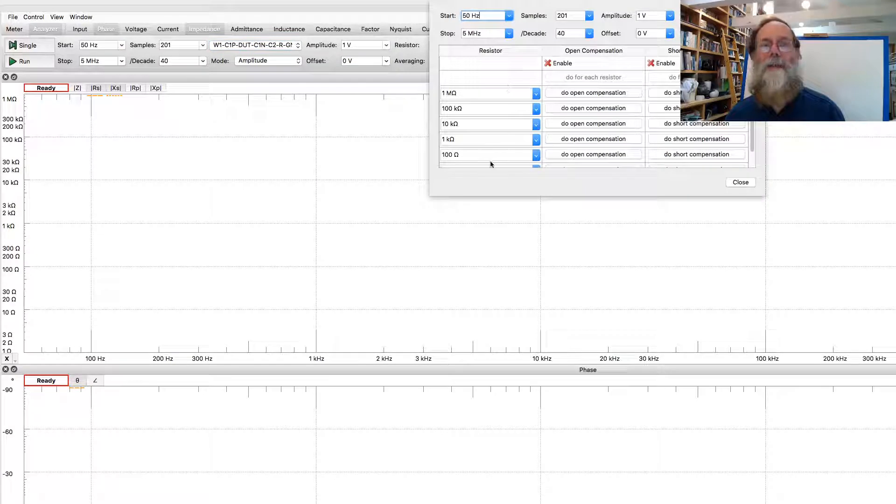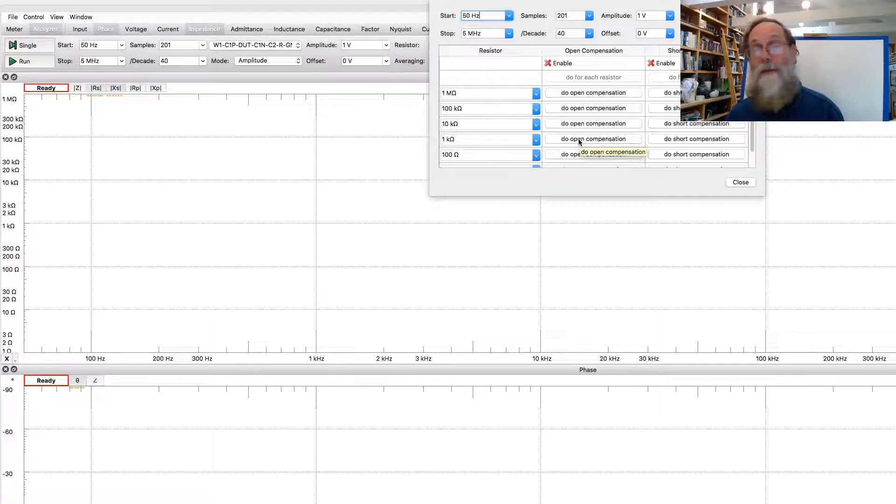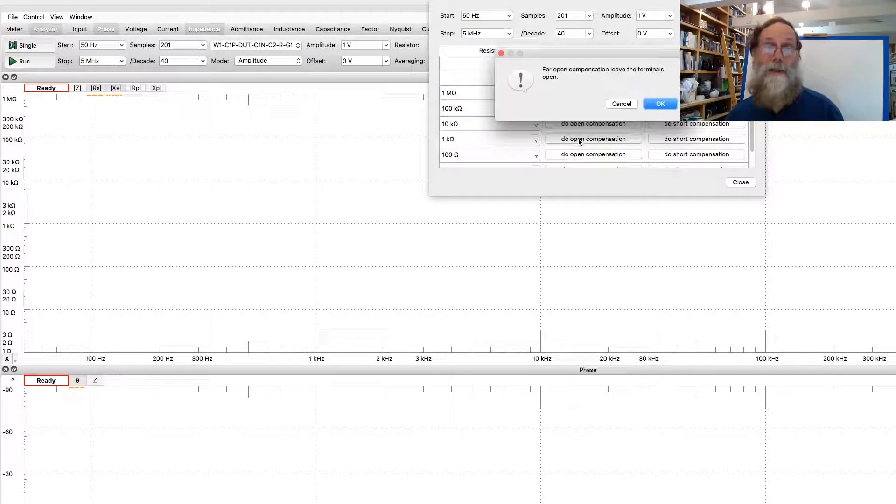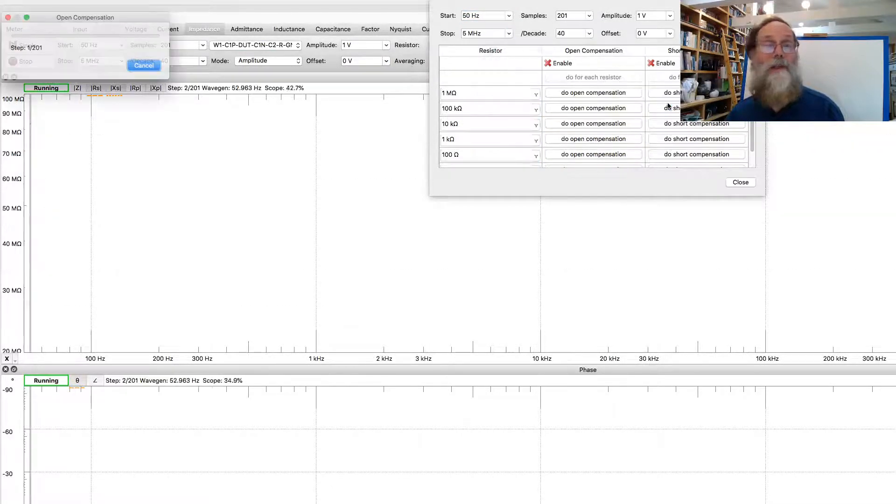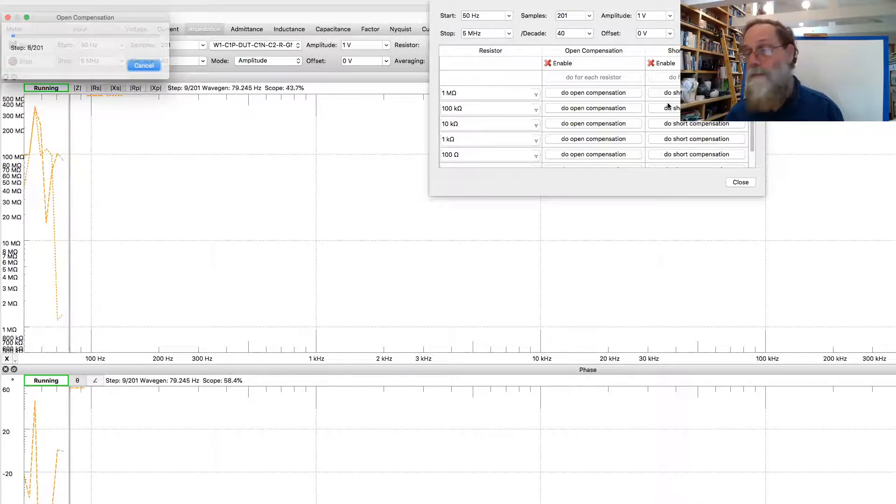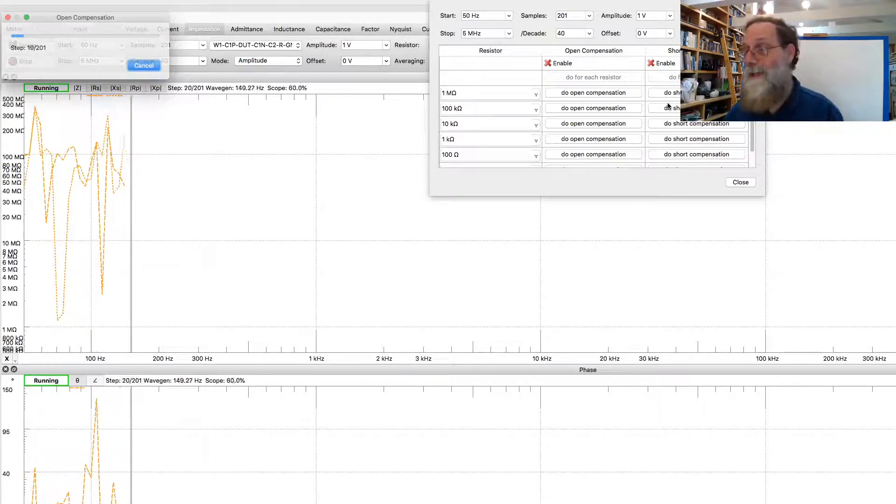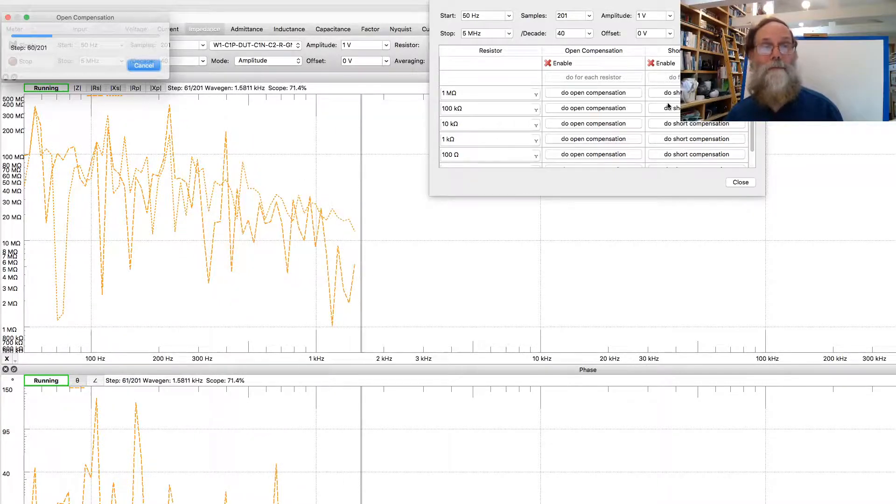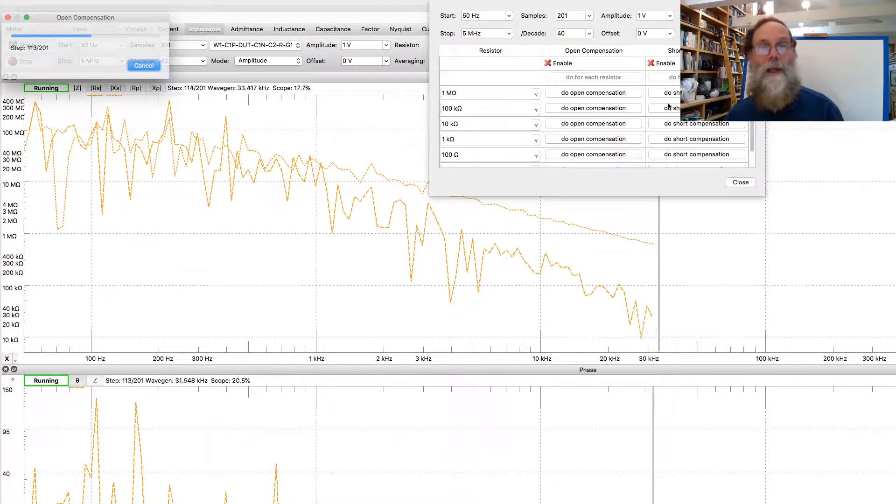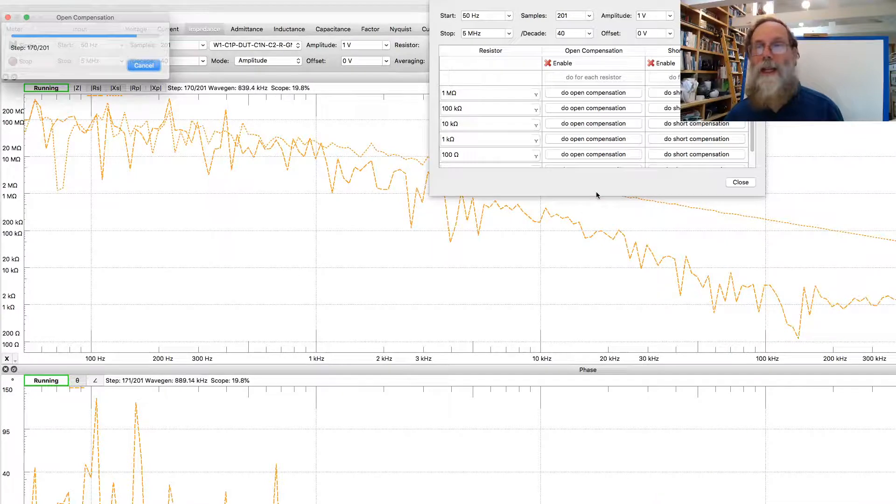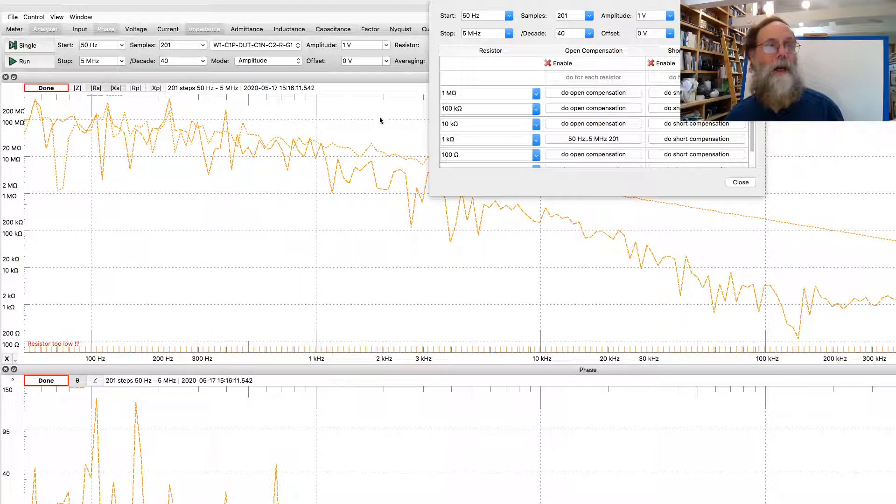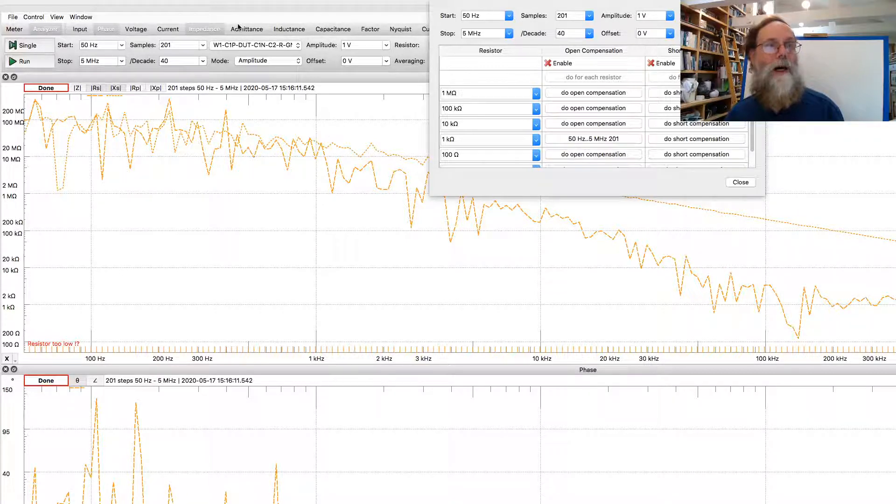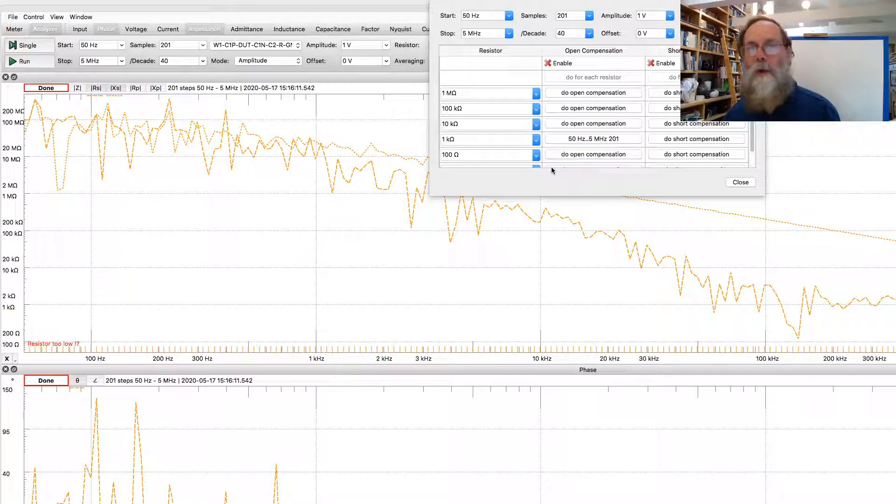So we want to get rid of those errors in the measurement to the extent that we can. And the compensation pop-up here allows us to do this. For the 1 kilohm sensor resistor, I don't have any device plugged in right now, so I can do open compensation. And what this does is measure what the impedance is at each of those points. Right now, it is reporting the real and imaginary parts. I can change that, I believe, to reporting just the magnitude.